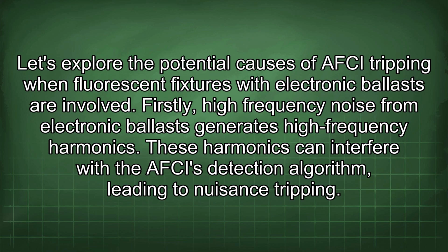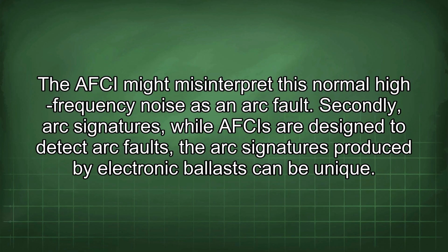Firstly, high-frequency noise from electronic ballasts generates high-frequency harmonics. These harmonics can interfere with the AFCI's detection algorithm, leading to nuisance tripping. The AFCI might misinterpret this normal high-frequency noise as an arc fault.